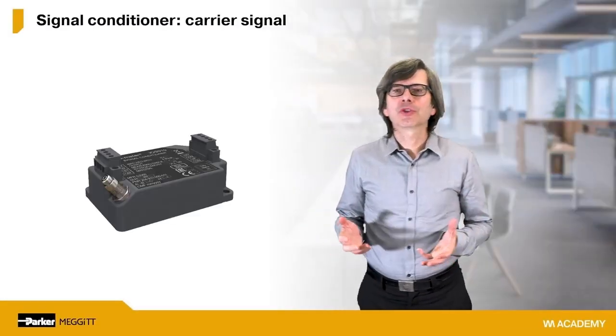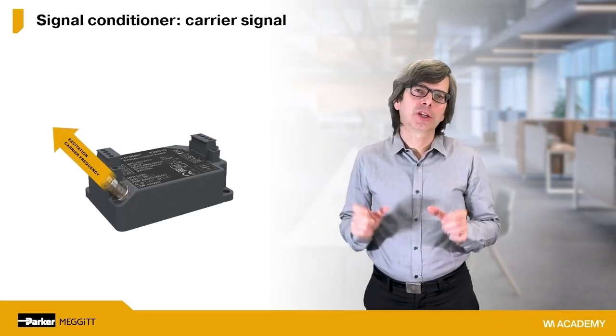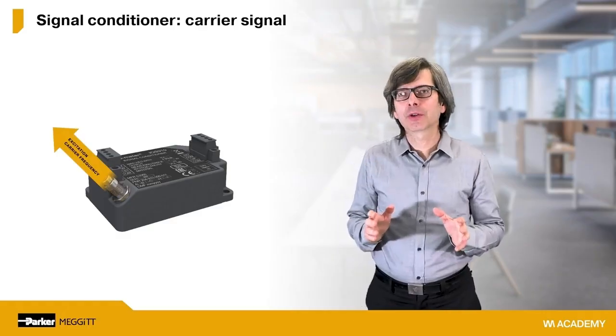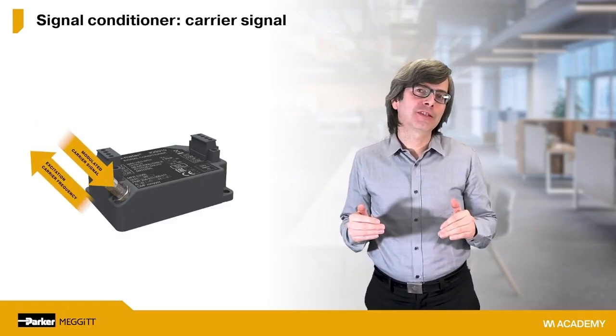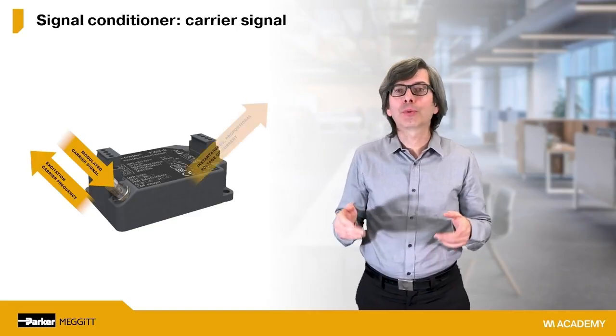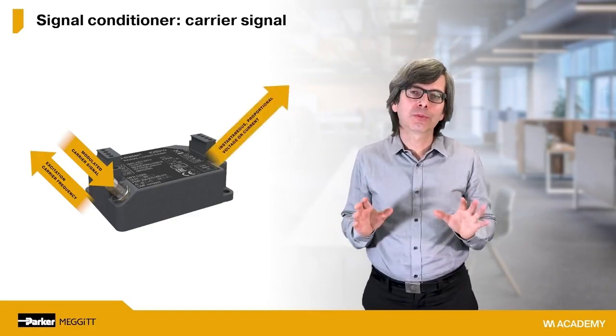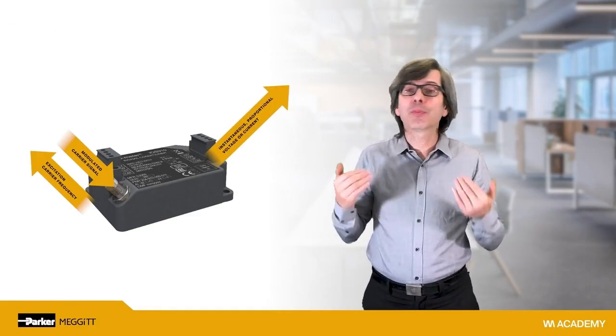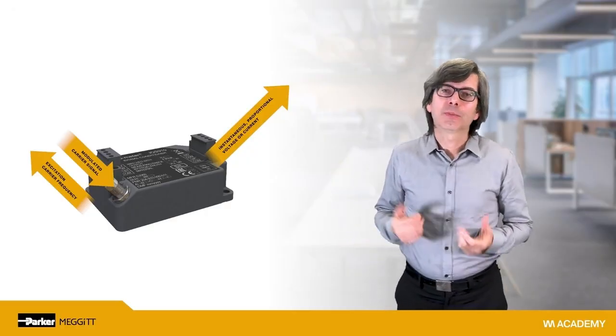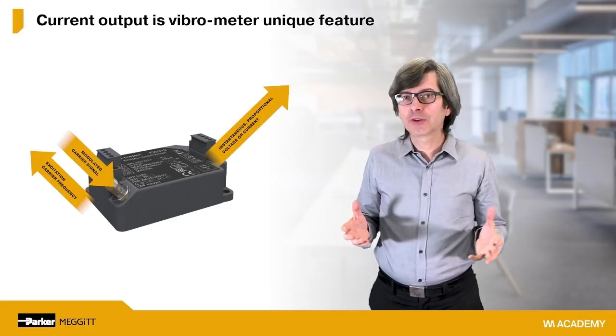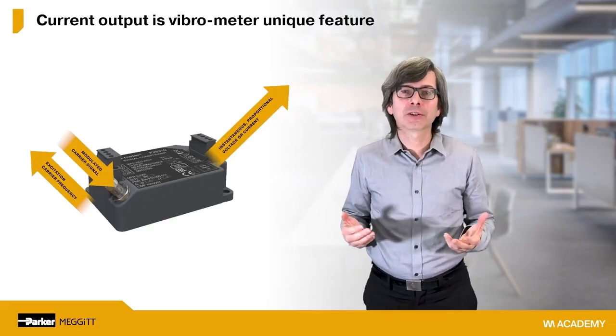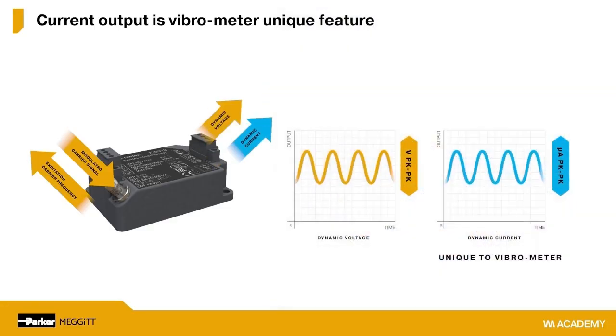Within a proximity measurement chain, the signal conditioner generates this excitation carrier frequency and also demodulates the signal returned by the probe to provide a voltage or current output that is going to be proportional to the gap. The most common choice is to use a proportional voltage output, but later in this lesson, we will discuss a unique feature of Vibro-Meter proximity systems, a key differentiator, which is the option to provide a proportional current output that can be selected instead of voltage if that's required.